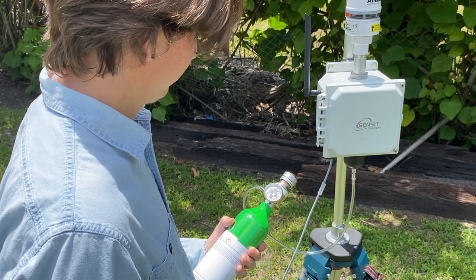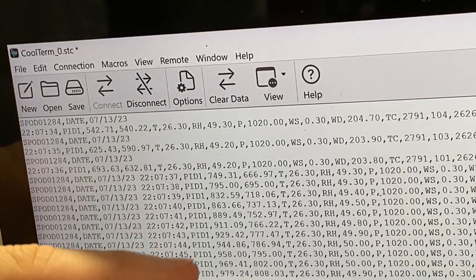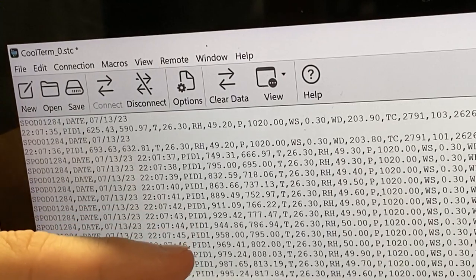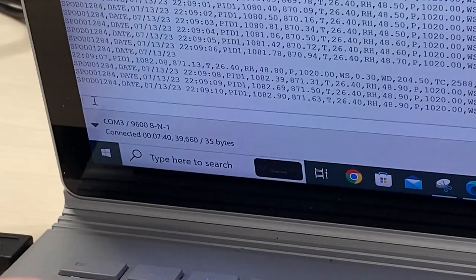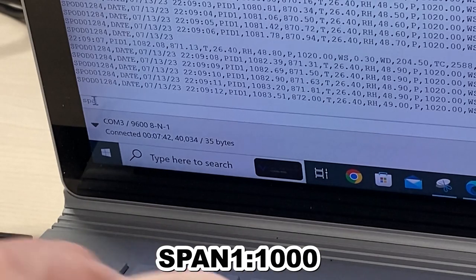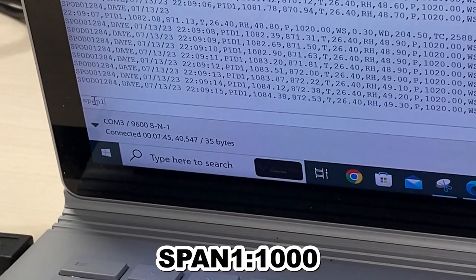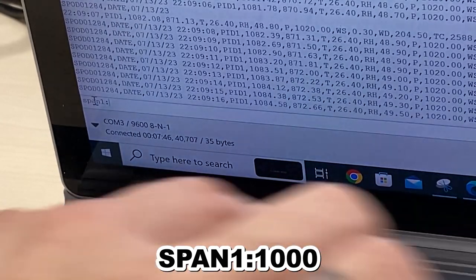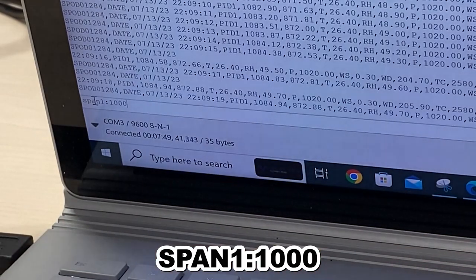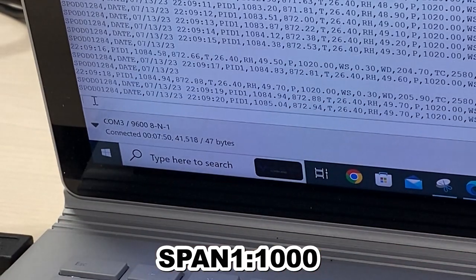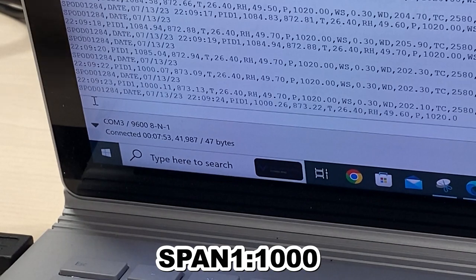Allow the sensor reading to stabilize in isobutylene. After the reading is stable, send the command "span 1:1000". The 1000 references the concentration in parts per billion of isobutylene used to calibrate the instrument.